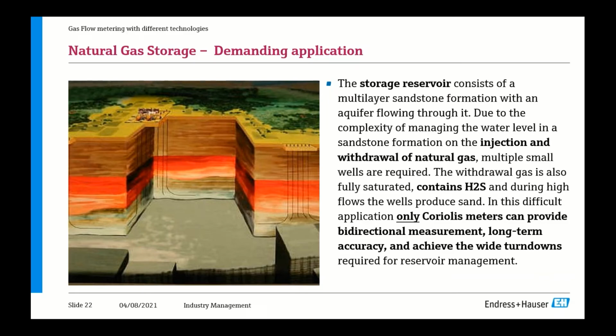In other words, the instruments are used to measure gas flow in two directions, pumping into the cavern and pumping out. For this kind of application, storage fields utilize Coriolis meters for injection and withdrawal measurement of natural gas. In this application, we will find multiple small wells, and the installations are very critical because they don't have a lot of space. They're very narrow spaces. There is a lot of pulsation and a lot of noise, and of course, we know that Coriolis meters are not affected by that.